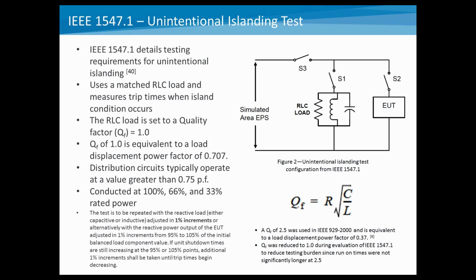There's a couple things to realize about that. It's done at 100%, 66%, and 33% of rated power. It's also quite difficult to detect exactly when you have that match condition, so it's done in 1% increments around 95 to 105% of the loading conditions. The other thing that's mentioned on this slide is something called a quality factor. The quality factor in the test is now equal to 1, and that basically is equivalent to a worst case power factor of 0.7.